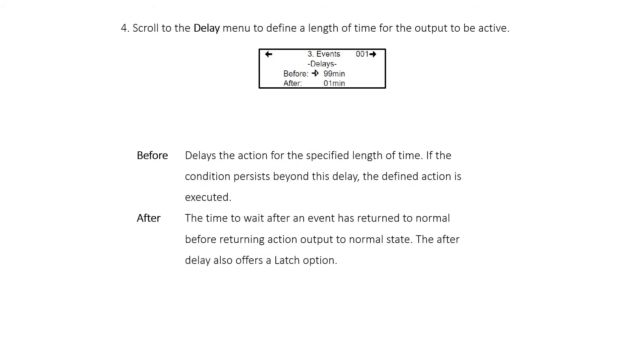Scroll to the Delay menu to define a length of time for the output to be active. Before delays the action for the specified length of time; if the condition persists beyond this delay, the defined action is executed. After is the time to wait after an event has returned to normal before returning the action output to normal state.